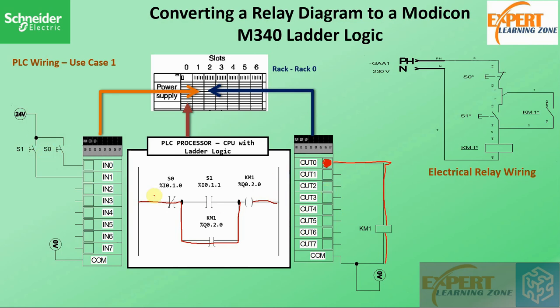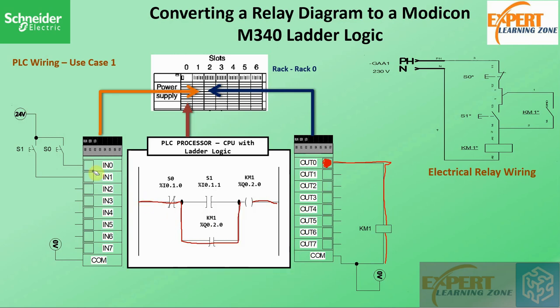When I press S0 — and remember this is normally closed — then this contact opens. While this switch is pressed and this contact opens, this line is broken. When this line is broken, current ceases flowing to the output. Our circuit is no longer complete, the circuit breaks open, and the coil is de-energized, so the system goes off.